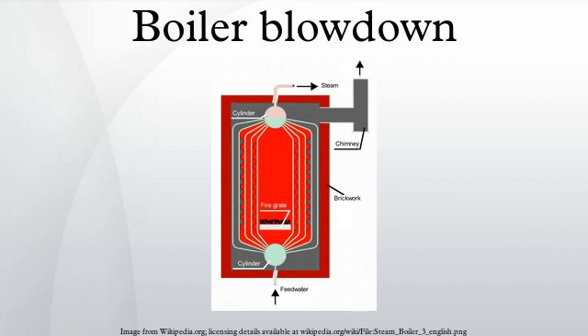Bottom blowdown: Some boiler water treatments cause precipitation of impurities as insoluble particles, anticipating those particles will settle to the bottom of the boiler before they become entrained in water circulating past the heat exchange surfaces. These water treatments often include compounds forming a sludge to entrap such particles.